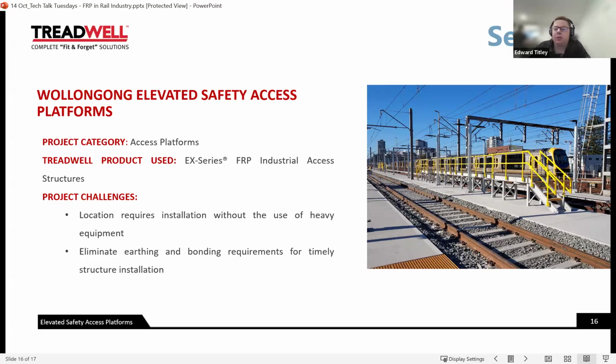Two reasons FRP was chosen here. One is the obvious one, the earthing and bonding aspect, given the very close proximity to the overhead wiring. Second was a constructability aspect. Now, this here is a refuge loop that you can see. That couldn't be powered down, couldn't be isolated, couldn't be taken offline. So it wasn't practical to try to bring in a metallic structure like galvanized steel and construct it there, because of the weight of that structure. This is all FRP: posts, structural members, handrail, floor grating, everything is FRP.